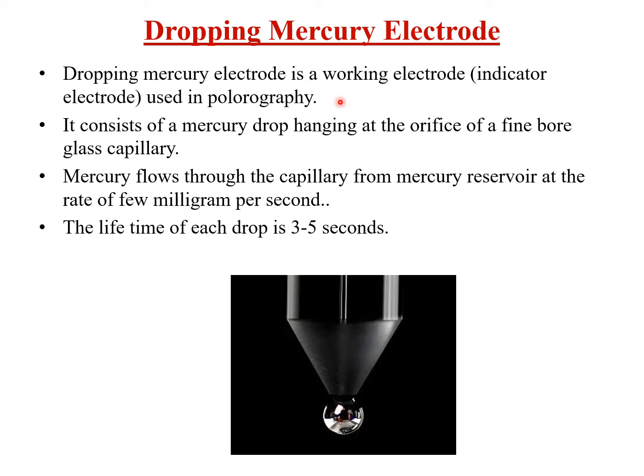In polarography we use two types of electrodes: an indicator electrode and a reference electrode. So this dropping mercury electrode is the working or indicator electrode. It consists of a mercury drop hanging at the orifice of a fine bore glass capillary, where a new mercury drop is formed at particular time intervals. The mercury flows through this capillary from the mercury reservoir at a rate of a few milligrams per second, and the lifetime of each drop is three to five seconds.